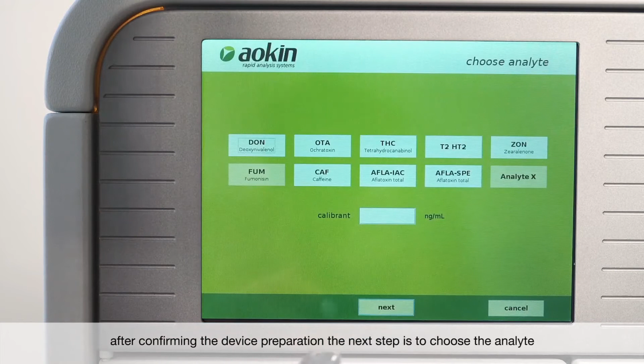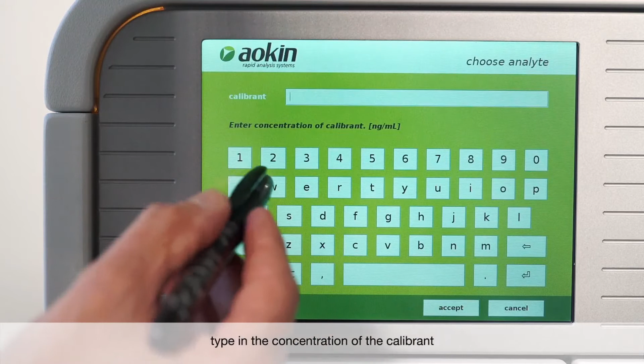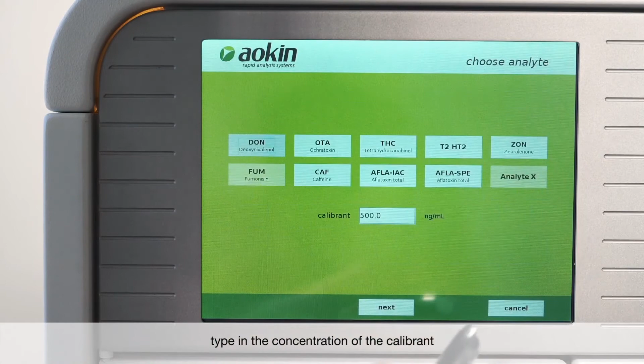After confirming the device preparation, the next step is to choose the analyte and type in the concentration of the calibrant. This is a sample tray with the position of the samples here and the positions for reagent set 1, reagent set 2. Each set consists of reagent 1 placed here, reagent 2 here, the standard and the diluent.